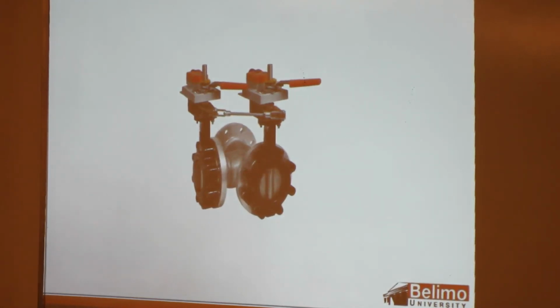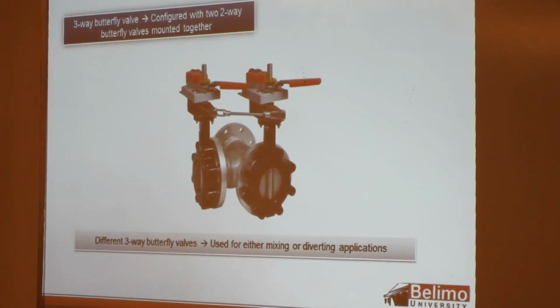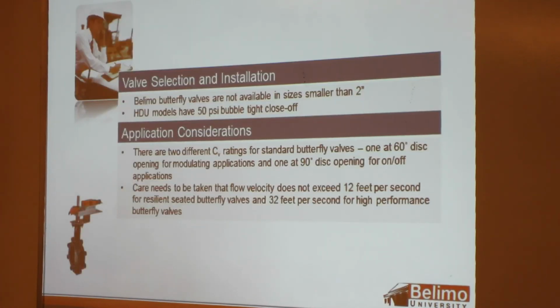We also have a 3-way butterfly valve. Basically, a 3-way butterfly valve is taking 2 2-ways and putting them on a T. You can see here we have the 2 actuators linked together, controlling the discs on each side. And those discs are going to move opposite of each other. So if one's opening, the other will be closing. They can be used for either mixing or diverting applications.